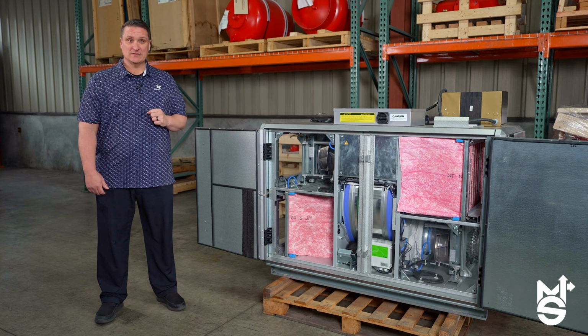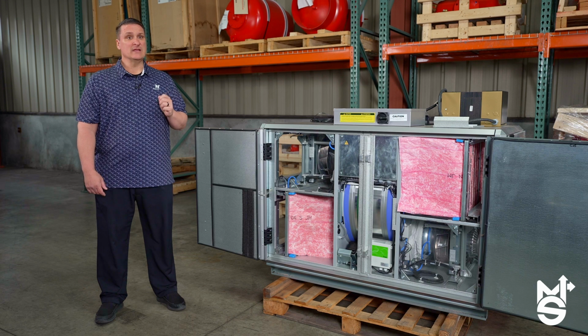Perhaps a fire smoke season where a carbon pre-filter is installed in the ERV. Transitional seasons, such as cottonwood seasons, could also be another reason to use a pre-filter. Swegon does not recommend a 2-inch pre-filter during regular operation due to the loading and high pressure drop causing extra energy usage. The Swegon ERV filter construction is very specific.